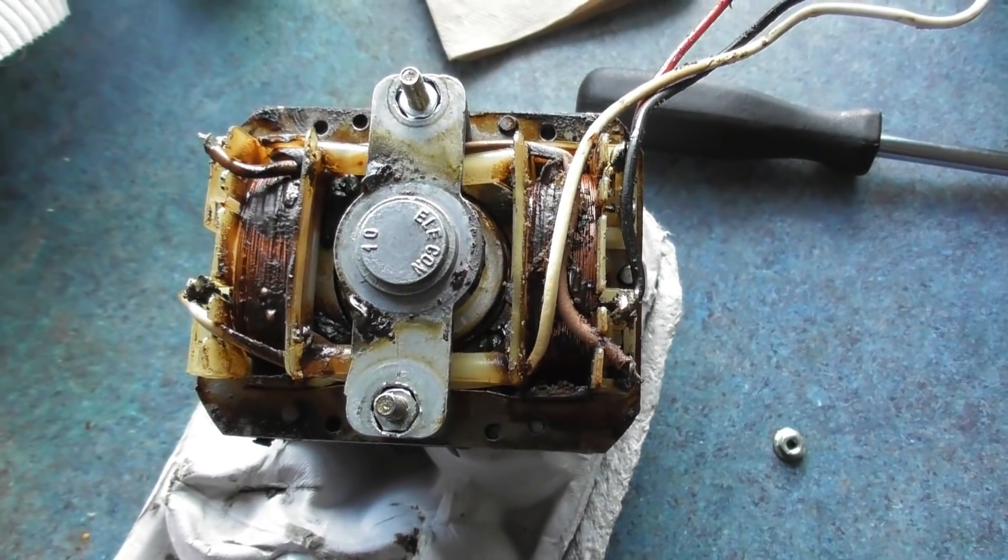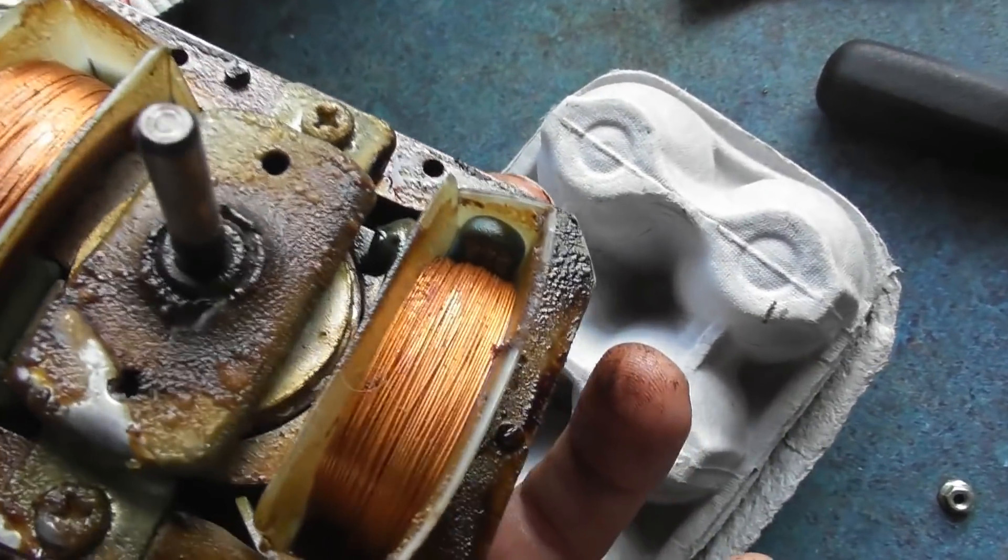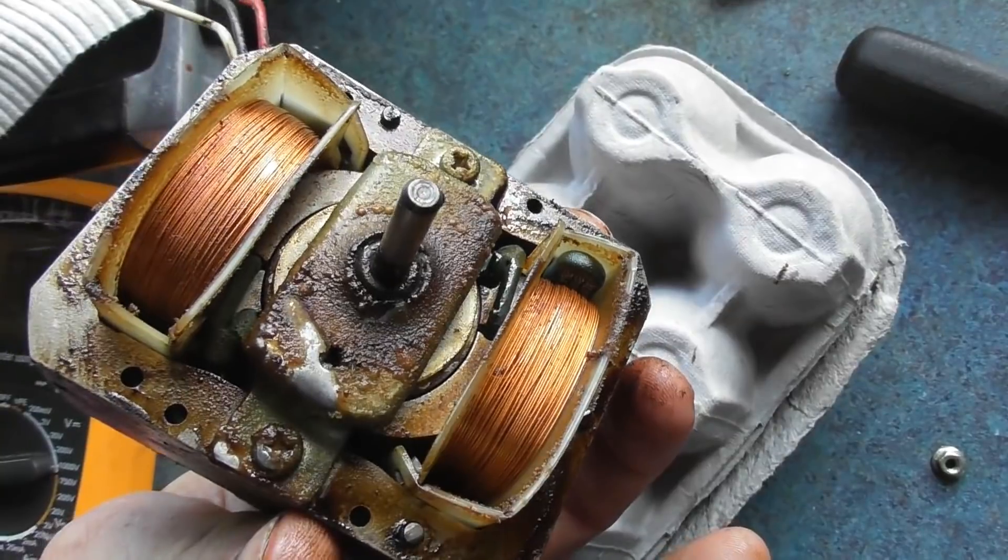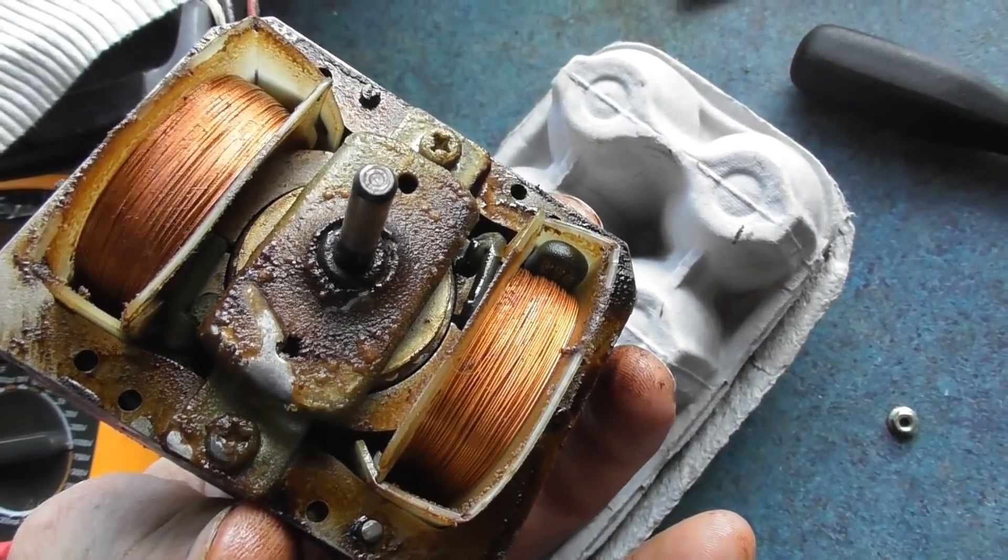One winding appears to be continuous, and the other one, there's a nasty little thermal switch in this thing here. Just notice this device here, and that appears to be open circuit, so I'm gonna bridge that out.